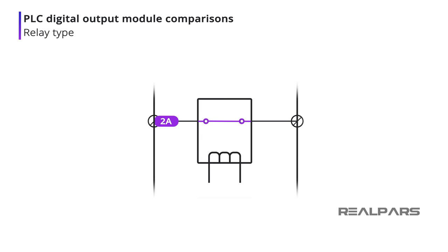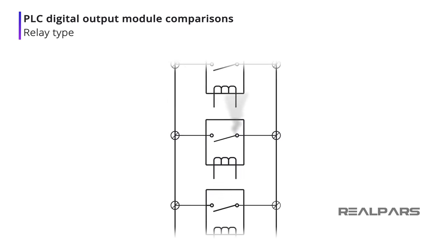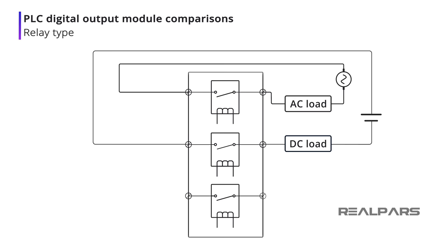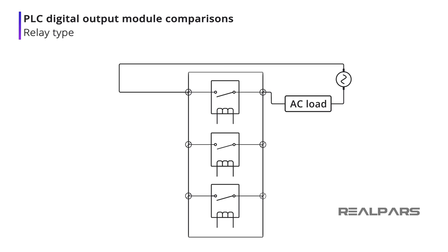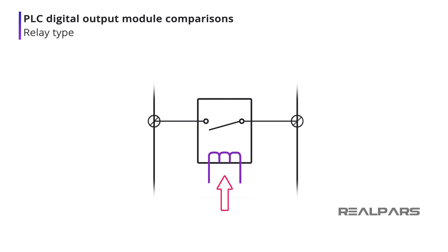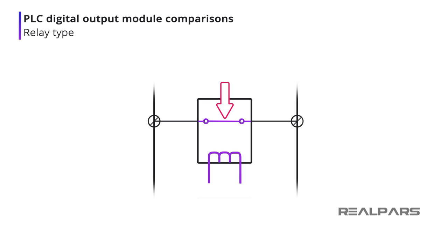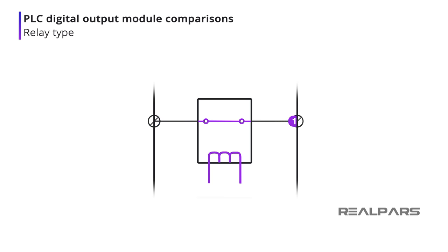Relays generally have a higher current rating than transistors, but as with any mechanical device, it will wear out with time. A relay module can operate AC or DC loads, or both. Relays provide electrical isolation between the load and the PLC. Relays are slow acting, with typical response times of 10 milliseconds or greater. Closed relay contacts are almost 0 ohms, thus ensuring no voltage loss.